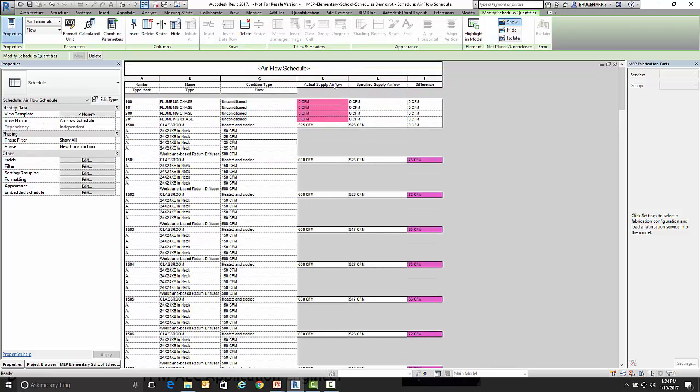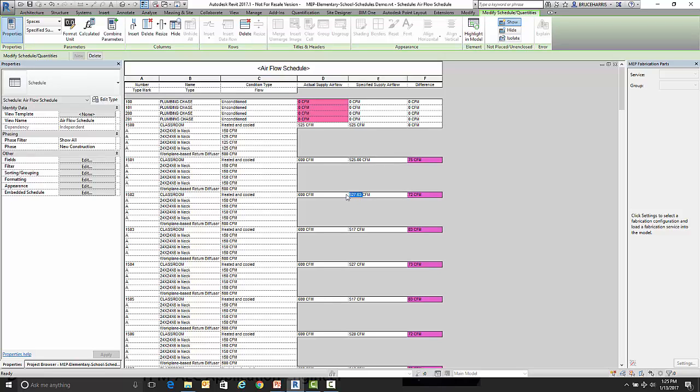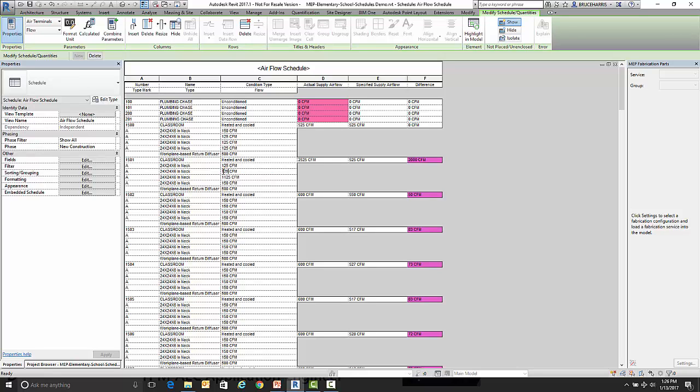Now as I come down my different rooms here, I can click on it and see what my specified airflow is. Change it to whatever I want. 525 is fine for that. And I'll round that one up to 550. And then I could come in and adjust. So I know that right now I've got more than I need. So I've got three of them that need to go down to say 125. So now you can see that I've got that exactly balanced in that room.